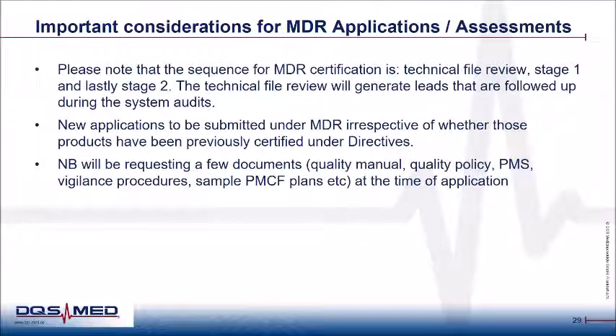It's very important for the assessment under MDR that the sequence is absolutely to first assess the technical file, and then move on to the stage 1 and then the stage 2 on-site audit related to MDR. The technical file assessment provides information that has to be verified during the on-site assessment, and verified against the system that you have implemented for the products.